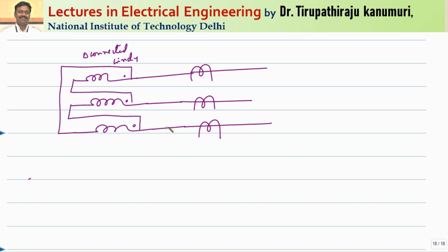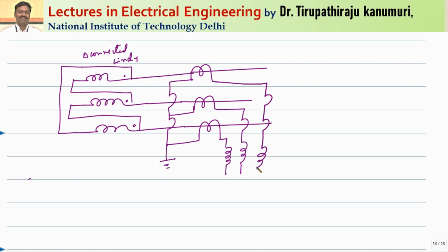In this case also the connection will be similar to what is drawn above. These 3 windings will be connected in star. It will be connected like this, this will be connected here and this point will be earth. These 3 are connected to the overcurrent relays. Again same thing, there is one more overcurrent relay and here also. Generally the overcurrent relay setting will be made between 50% to 200%.